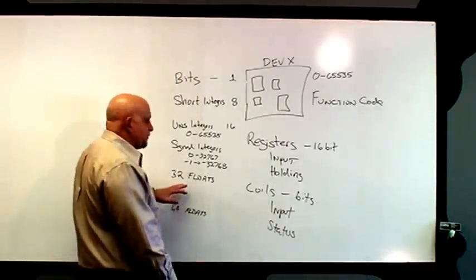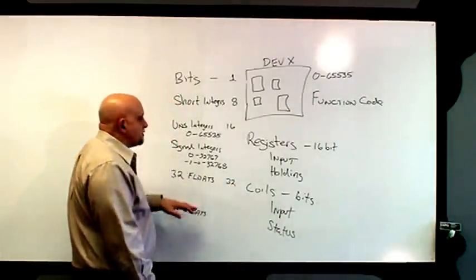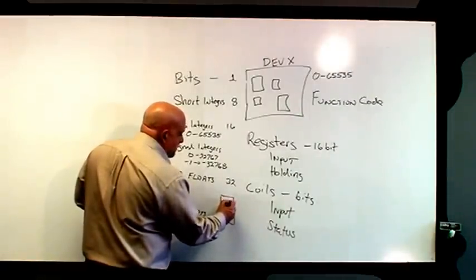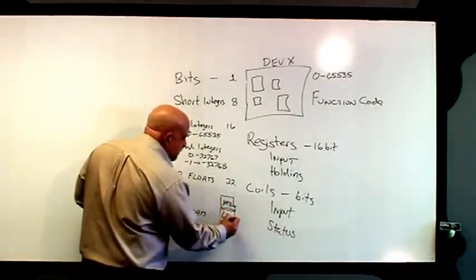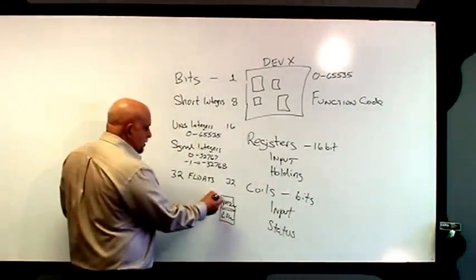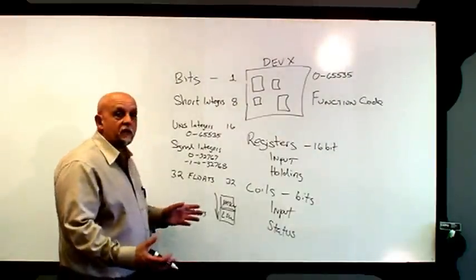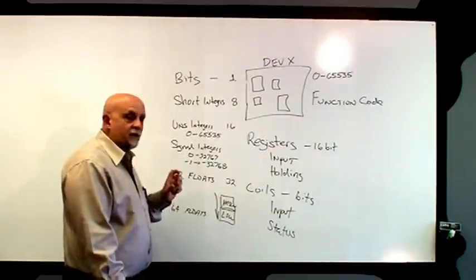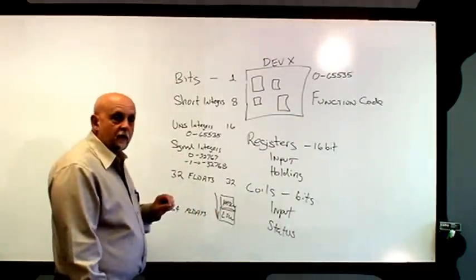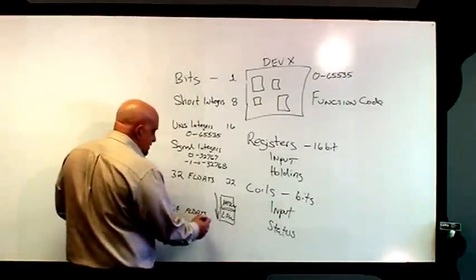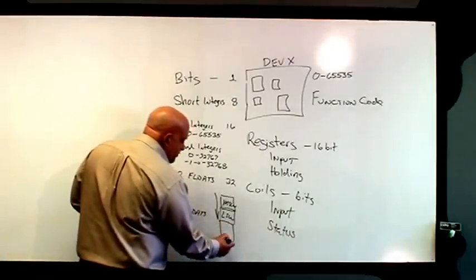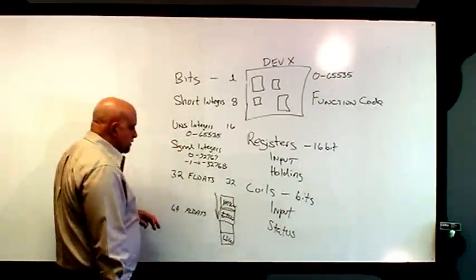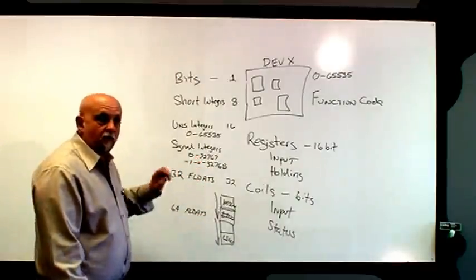For 32-bit floats — 32 bits — that gets represented by concatenating two registers together: the MSW (most significant word) followed by the LSW (least significant word). The key is you've got to read these together, because if you read one and then the next in a separate read, they could change since they're part of the same value. For 64-bit floats, you concatenate two more registers — now you have four total, still with the MSW first and the LSW last — and you must read all four together.